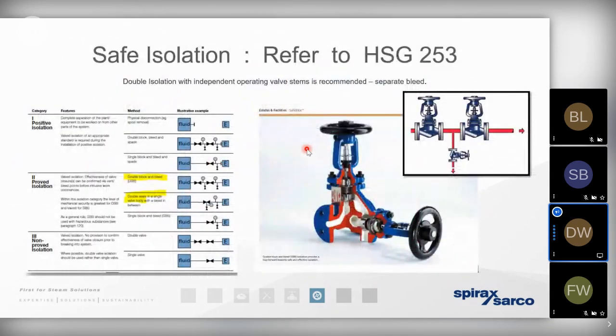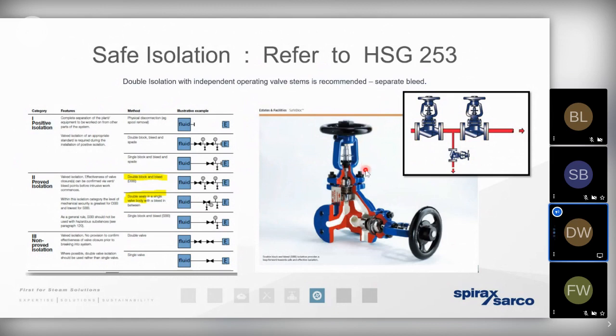Safe isolation is critically important. Steam valves are typically metal-to-metal seated, so unless we have excellent steam condition, those valve seats can become eroded, allowing a bypass of high-pressure, high-temperature steam. A failing single isolation valve presents a health and safety hazard. By moving to double isolation — two valves in sequence with a bleed valve between them — we protect the operator performing maintenance and have a telltale indicating steam is being vented away. We can also bring all three valves together into a single casting, making it very quick and easy to upgrade the health and safety provision within the original valve face-to-face dimension.